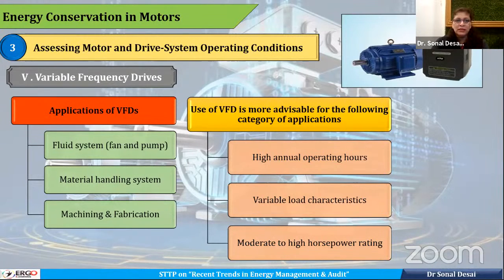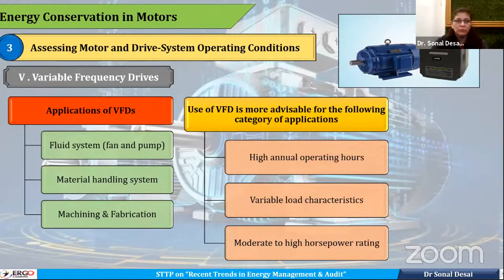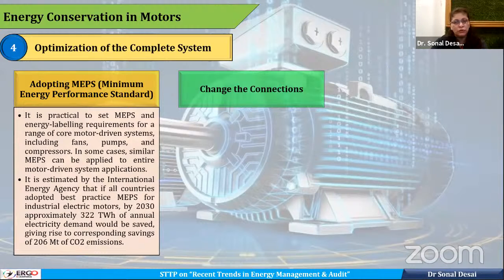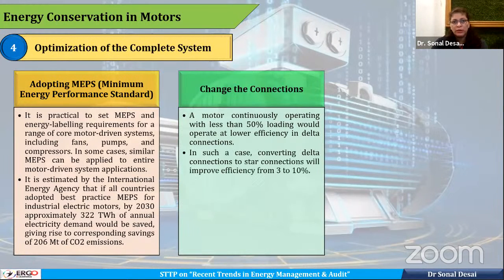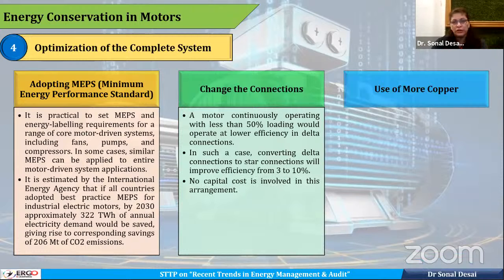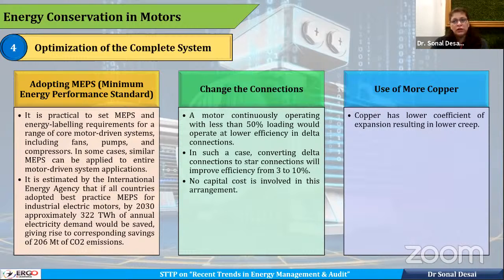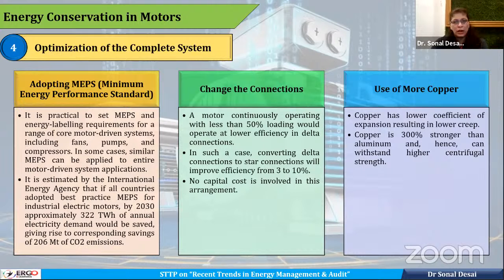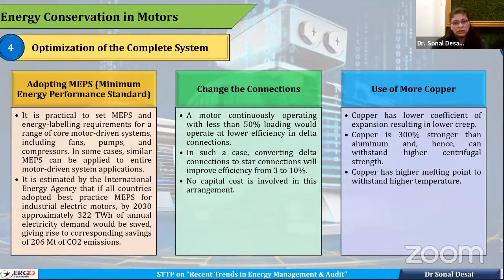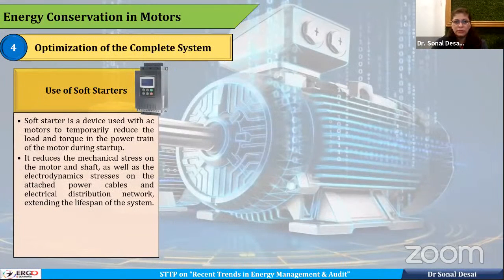If we talk of optimizing the entire motor assembly with the pump or with any driven system, then always go with the minimum energy performance standard, follow that. Change the connections that can save energy with minimum operating cost or no cost involvement. When we change the connection, it can also improve the efficiency. Whenever we think of rewinding, go with more copper. That will also add to the performance. Use soft starters for motors, that will have easy startup. It will have a lower stress on the lining, and that is advisable.